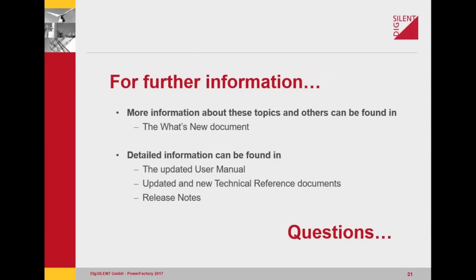There is a question: can the new user-defined modules be used for LVRT scenarios to simulate the voltage of an external grid? So I believe by user-defined modules, you are referring to quasi-dynamic simulation models. The answer would be no. You would need to go to an RMS or EMT. Well, usually it's going to be an RMS type simulation. User-defined modules for quasi-dynamic simulation should be used for medium to long-term analysis, and definitely LVRT studies are not part of this.